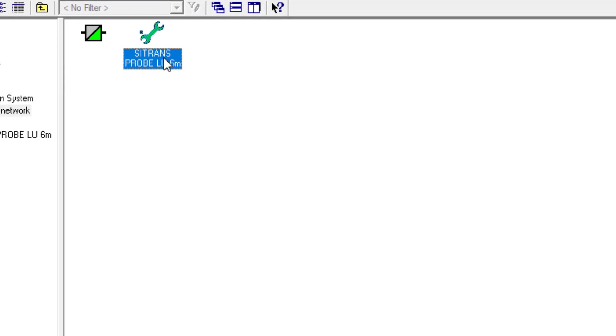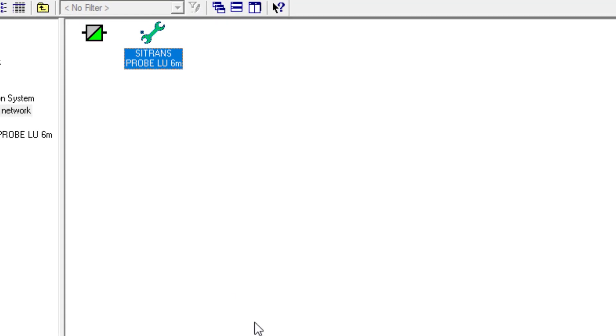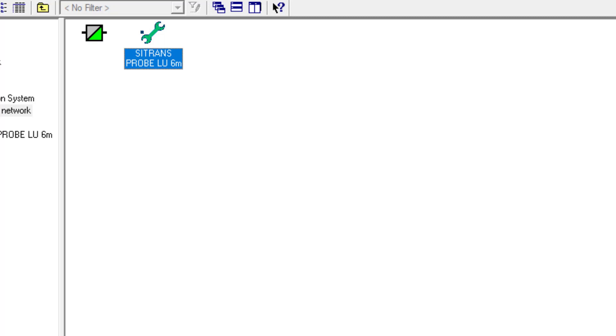And as I said, if you go back to PDM, we can see there's a maintenance request. So there you go, nothing wrong with using generic GSDs. Just wanted to show you them. Of course you can carry on using the manufacturer GSDs, is absolutely no issue using both, but you are going to have issues trying to get the devices replaced at a later date if you've got obsolescence problems. So that was an overview of adding a Profibus PA device to a transparent DP to PA coupler on TIA portal. Thanks for listening and I hope you found it useful.